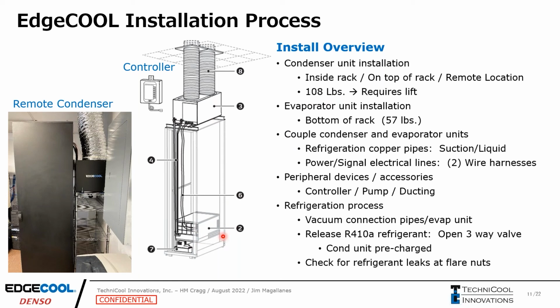The condenser and the evaporator are coupled together with refrigeration pipes, copper pipes, 1/2 inch for the suction pipe and 3/8 inch for the liquid side. From there, you put in the electrical wire harnesses. One has power going to the evaporator unit, and the other one has a signal line for the evaporator fan system. The condenser unit has a 5-20 plug on it, so you plug that into any dedicated outlet. Once you have that connected, you hook up your peripheral devices and accessories: the controller, the ducting that's required, and a condensate pump that goes inside the rack.